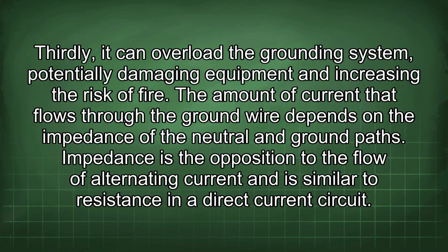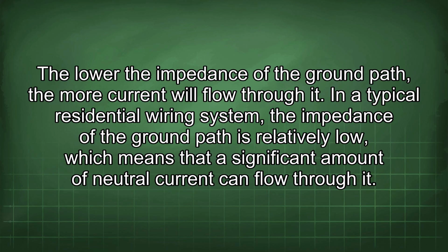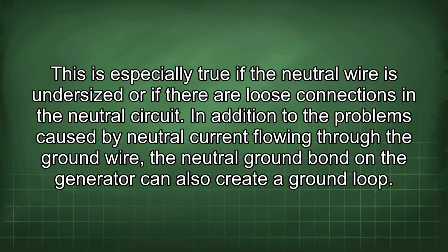The amount of current that flows through the ground wire depends on the impedance of the neutral and ground paths. Impedance is the opposition to the flow of alternating current and is similar to resistance in a direct current circuit. The lower the impedance of the ground path, the more current will flow through it. In a typical residential wiring system, the impedance of the ground path is relatively low, which means that a significant amount of neutral current can flow through it. This is especially true if the neutral wire is undersized or if there are loose connections in the neutral circuits.